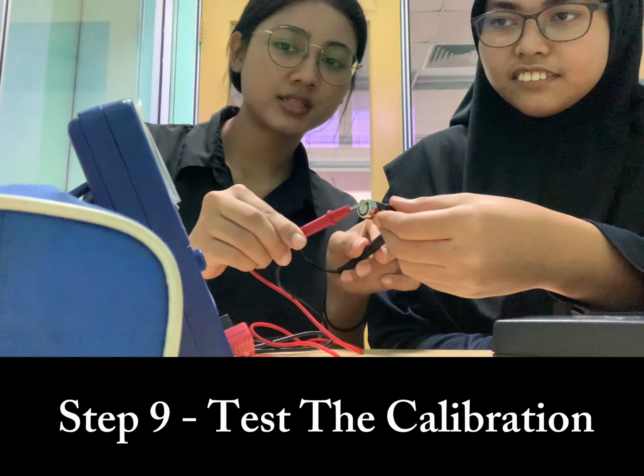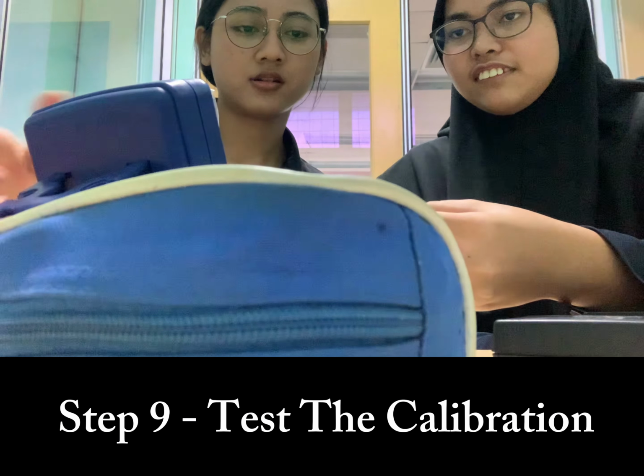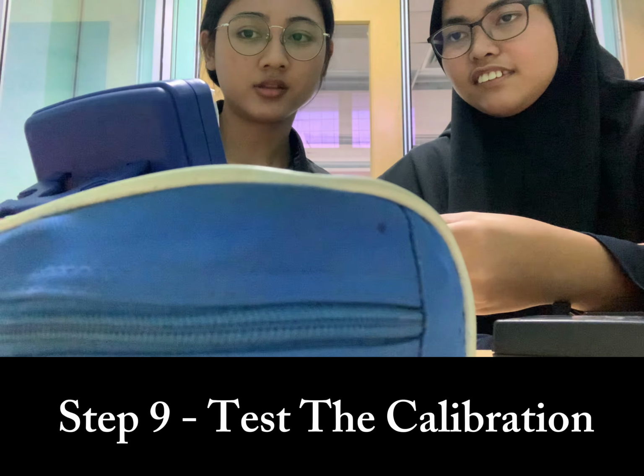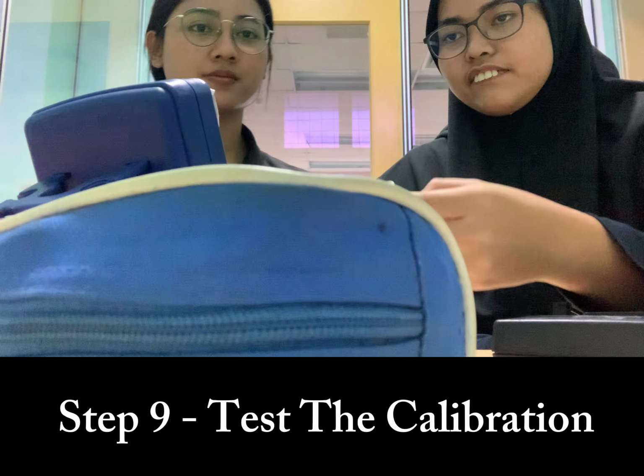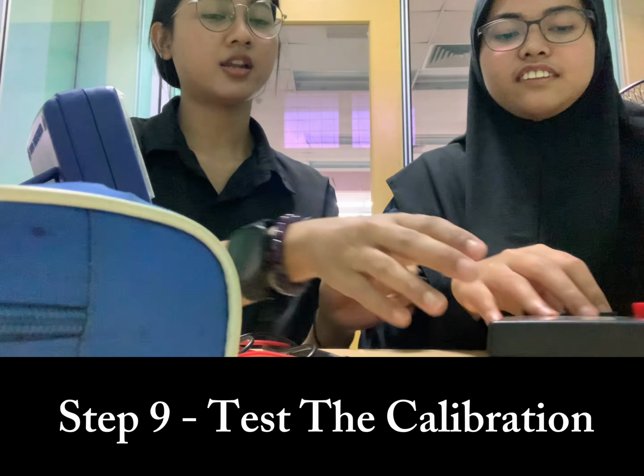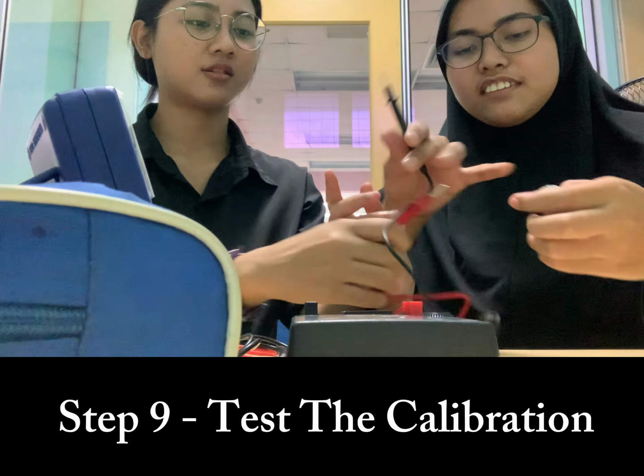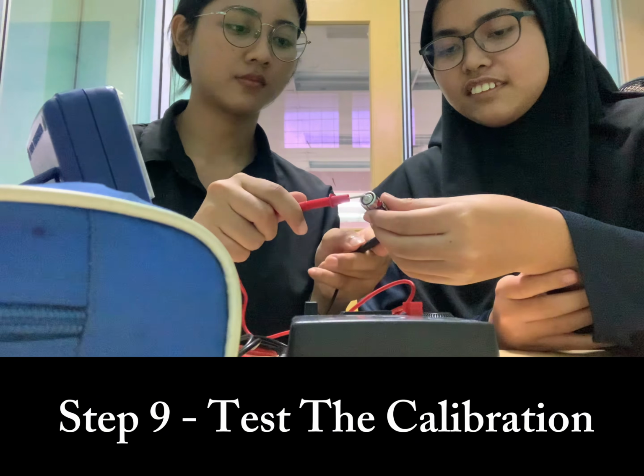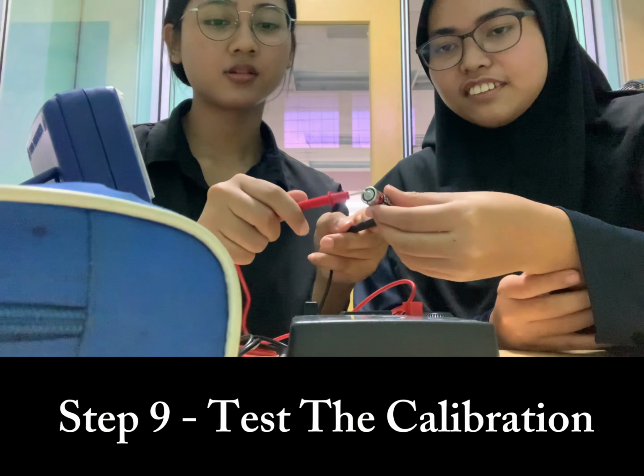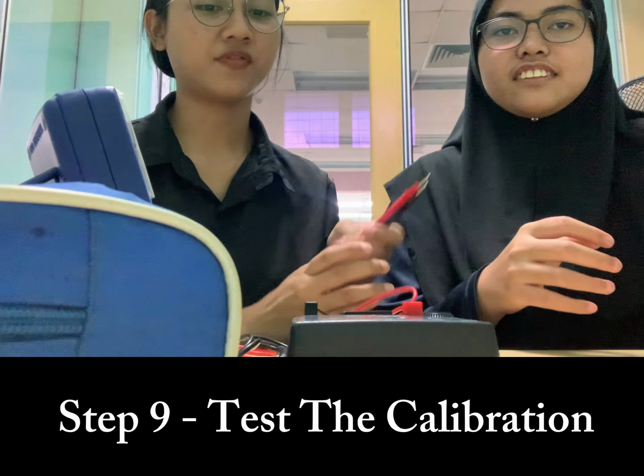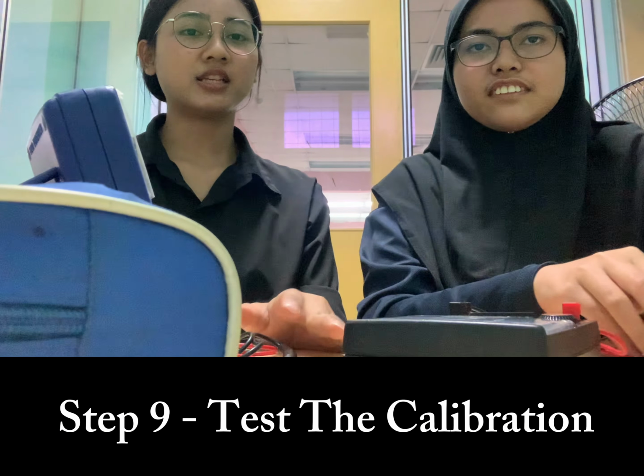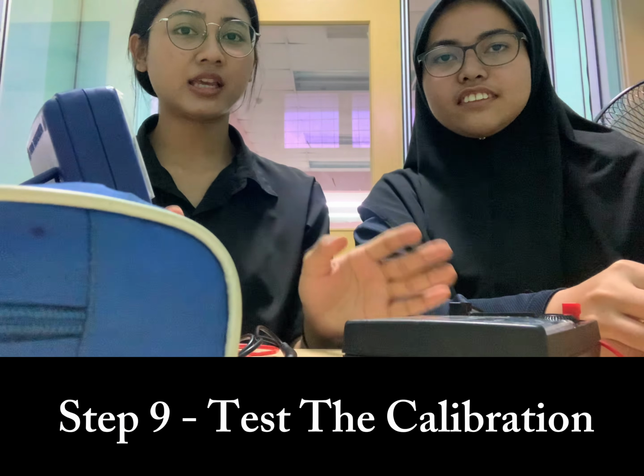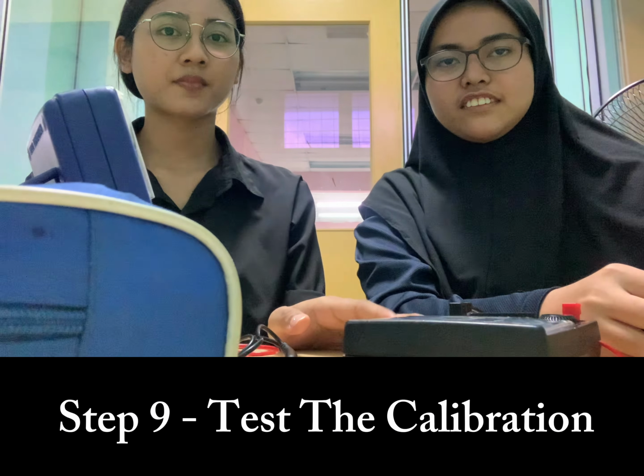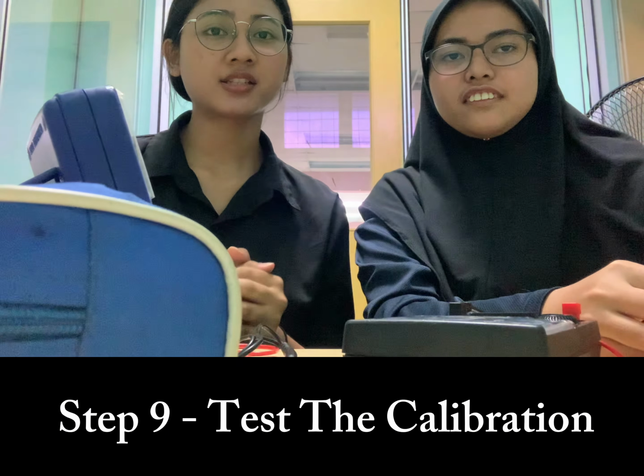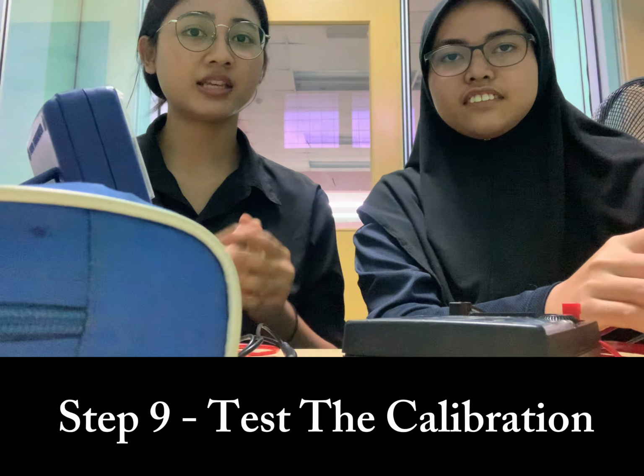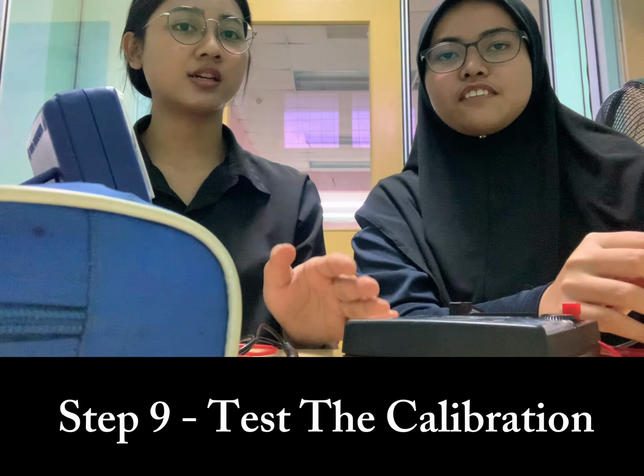The reading is 1.6. Now we use another multimeter to check. So the reading is 1.5. The readings are almost the same, which means it is functioning. Why do we need to test the calibration? It is because incorrect calibration can lead to inaccurate measurements.